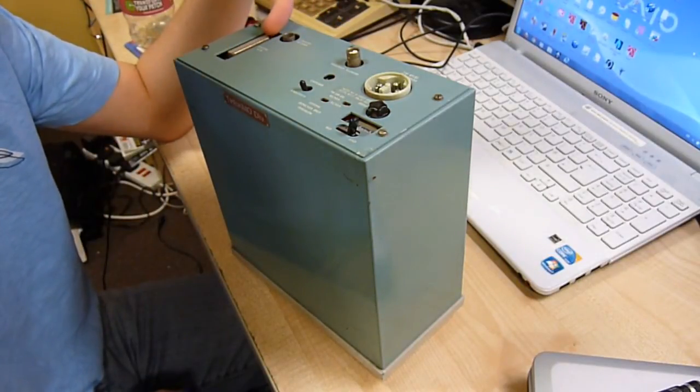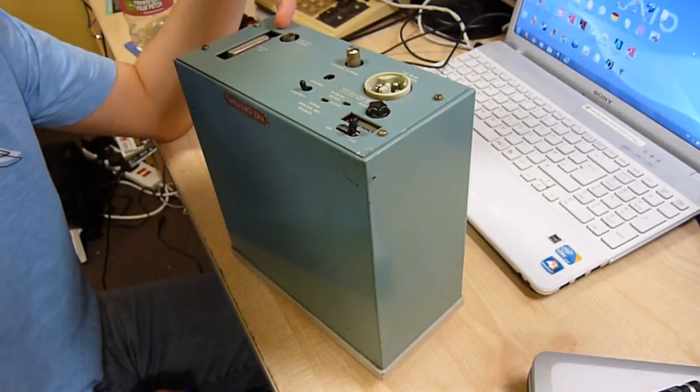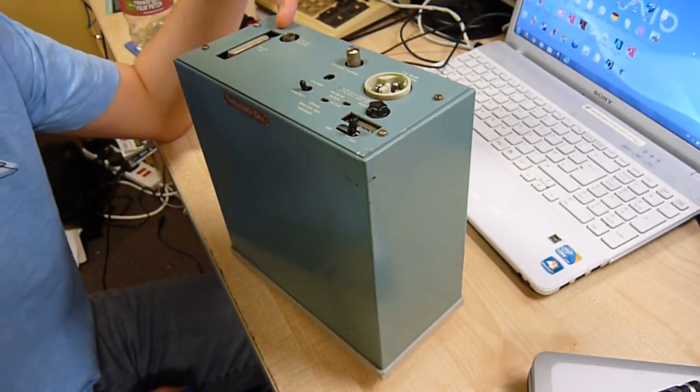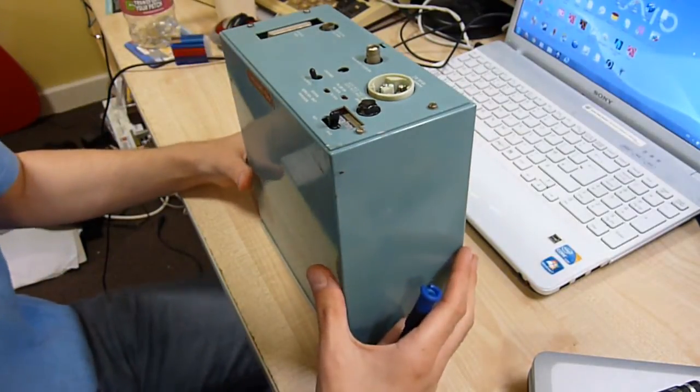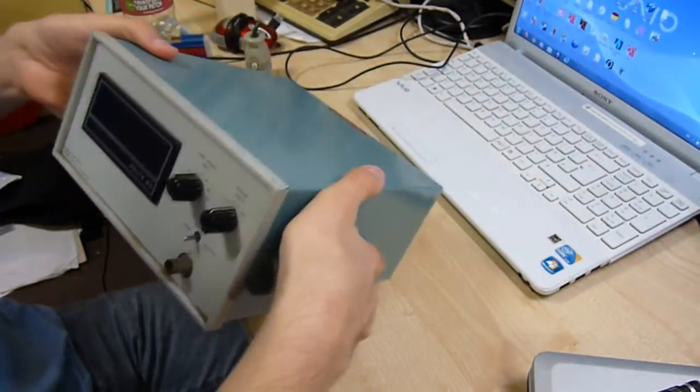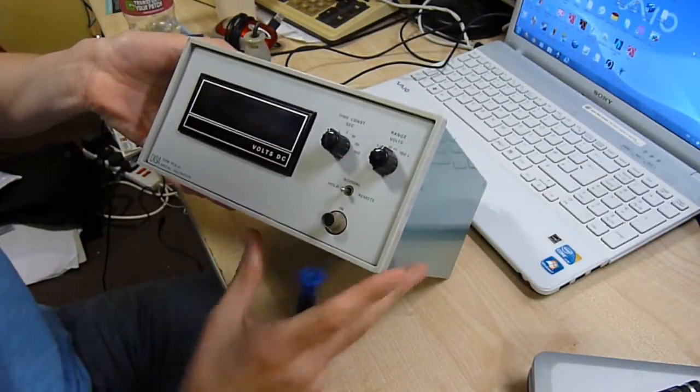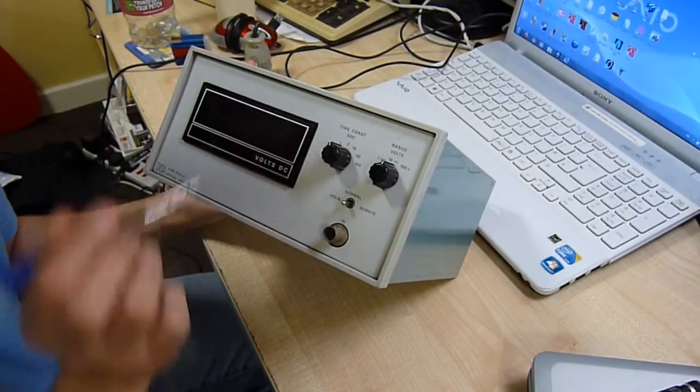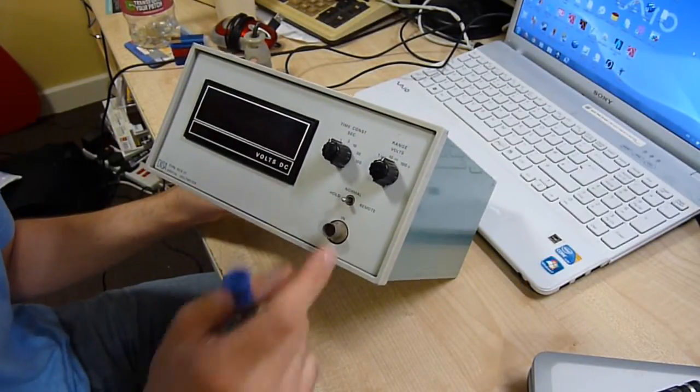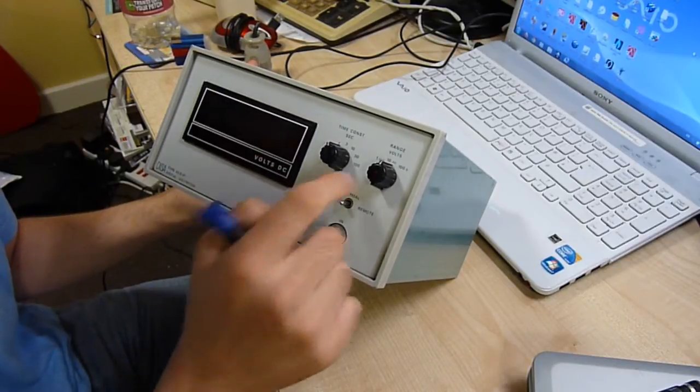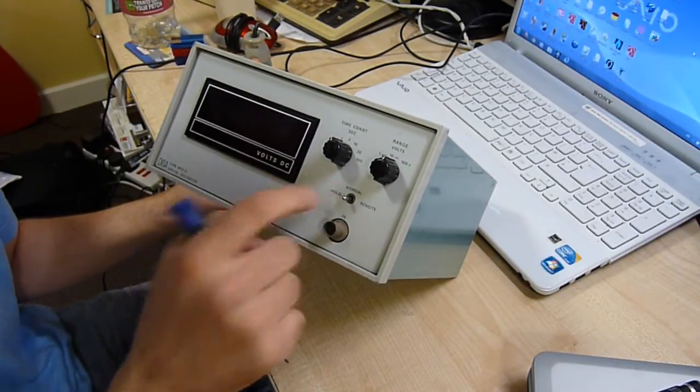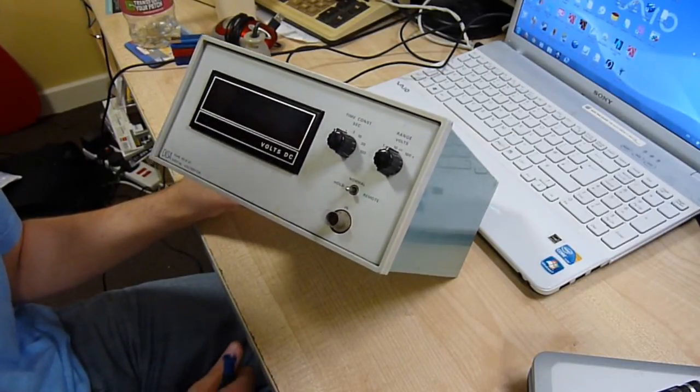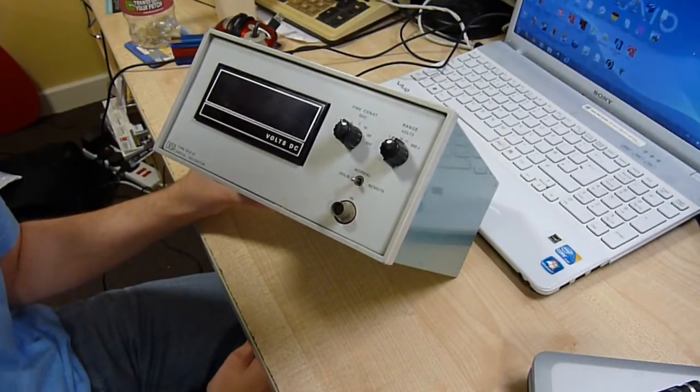OK, I appreciate this is lab equipment, but exactly why does lab equipment this old need a computer interface on it, bearing in mind it doesn't actually have a microprocessor inside it anywhere? On the front we have the volts range which is up to a hundred volts from one volt, and time constant, maybe that's refresh rate, and then you have the input normal mode, remote mode for remote control, and hold mode, which I'm not sure what that does. I can find absolutely zero information on this on the internet.